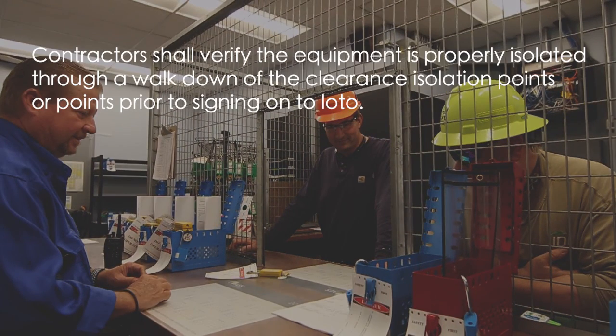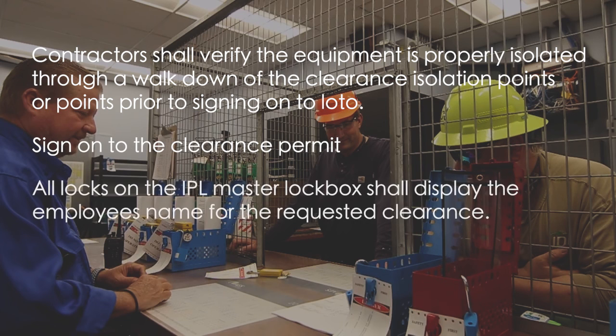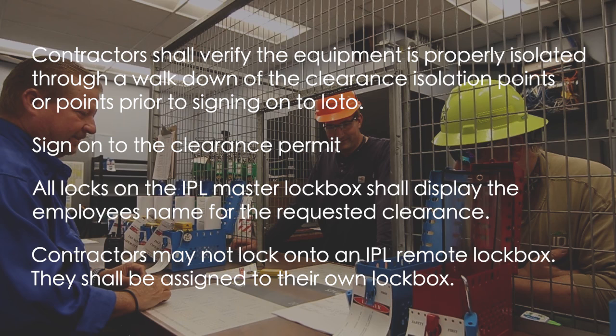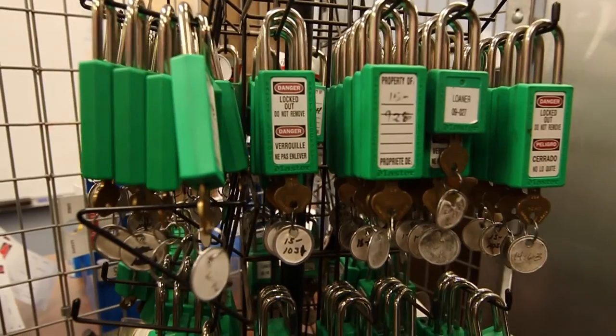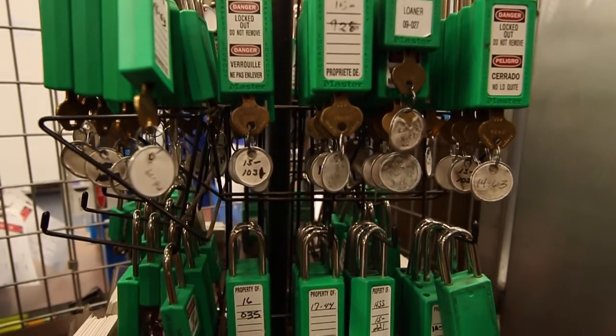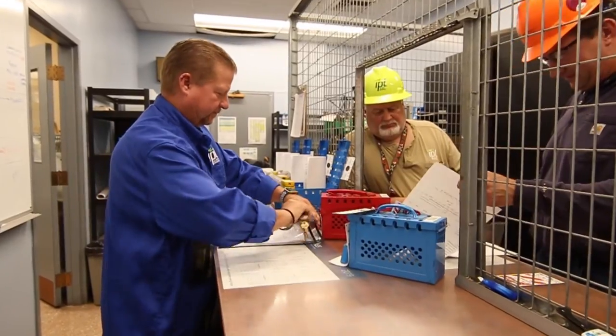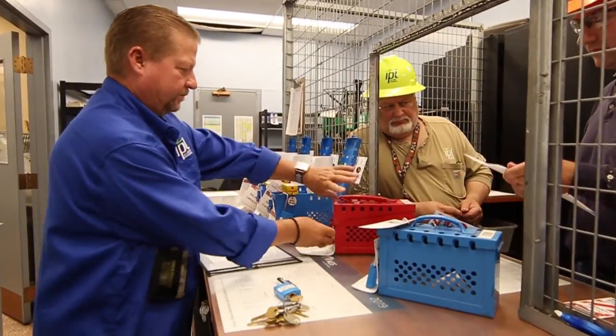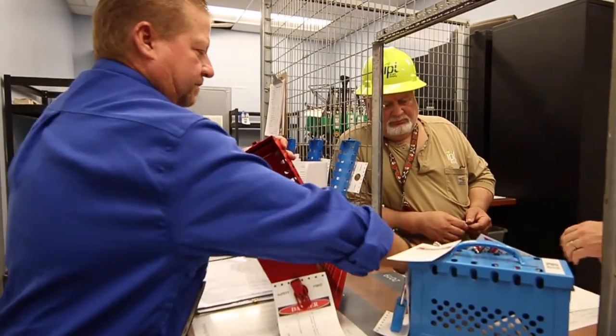Contractors shall verify the equipment is properly isolated through a walk-down of the clearance isolation point or points prior to signing on to LOTO. Sign on to the clearance permit. All locks on the IPL master lock boxes shall display the employee's name and contractor's name for the requested clearance. Contractors may not lock onto an IPL remote lockbox. They shall be assigned to their own lockbox. Contractor or loaner locks are green and keyed individually. Used by a contractor, the tag or label will identify the contractor's company name and the contractor's employee name.